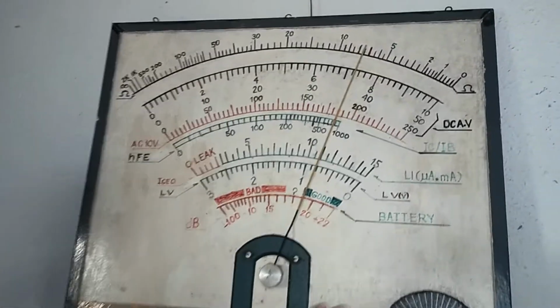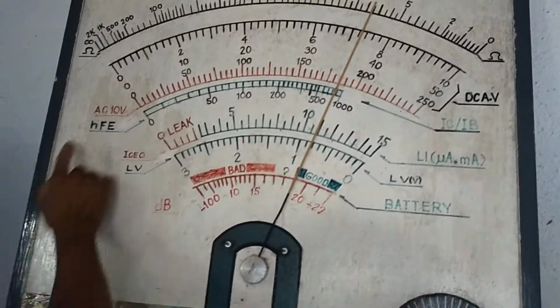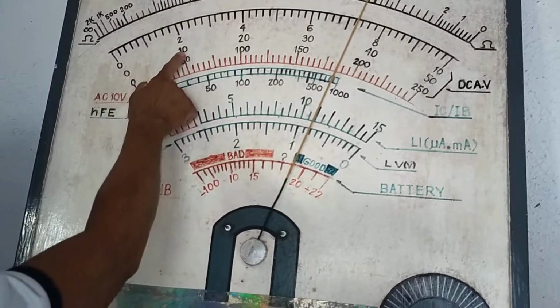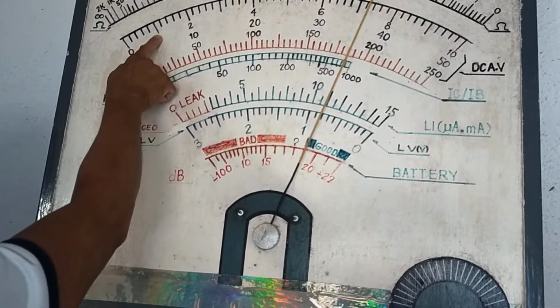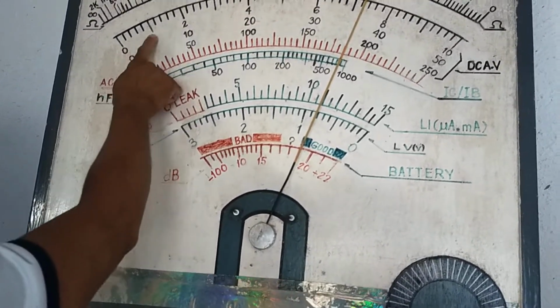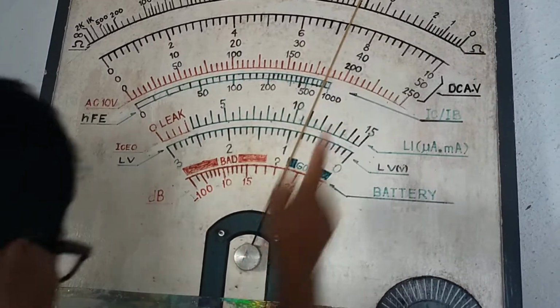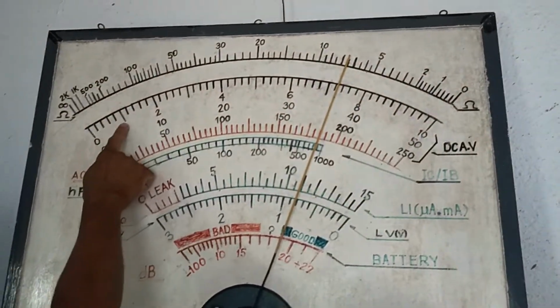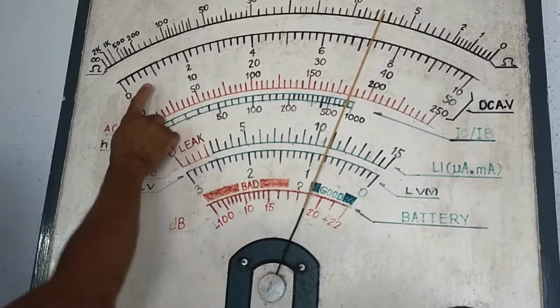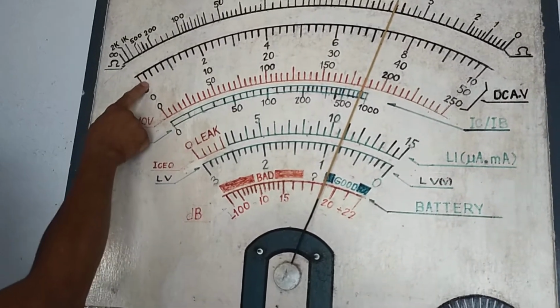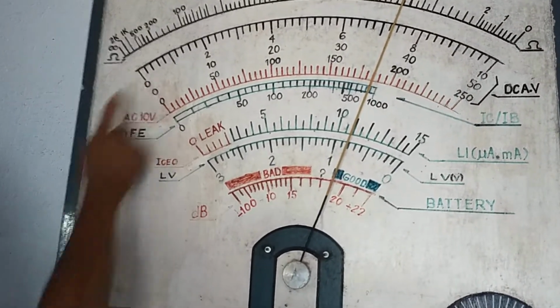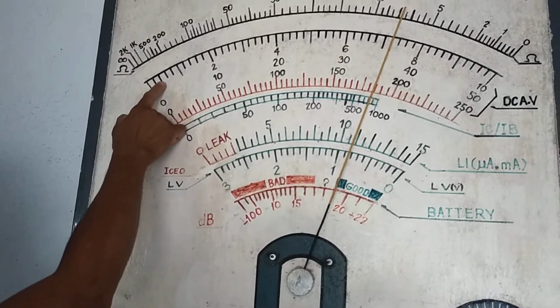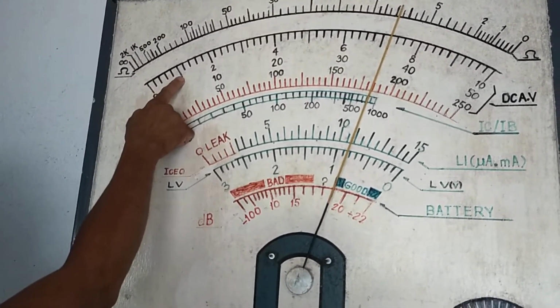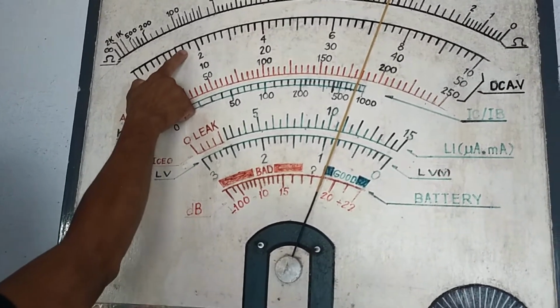But looking for the value for every division, and that is the calibration, if this is 10, this is 5. If this is 2, this is 1, di ba? Because we are now at 10 volts range. 10, 8, 6, 4, 2. Between 0 and 2 is 1. So, the calibration here, or the value for every division, is 0.2. 0.2, 0.4, 0.6, 0.8, 1, 1.2, 1.4, 1.6, 1.8, 2. So on and so forth.